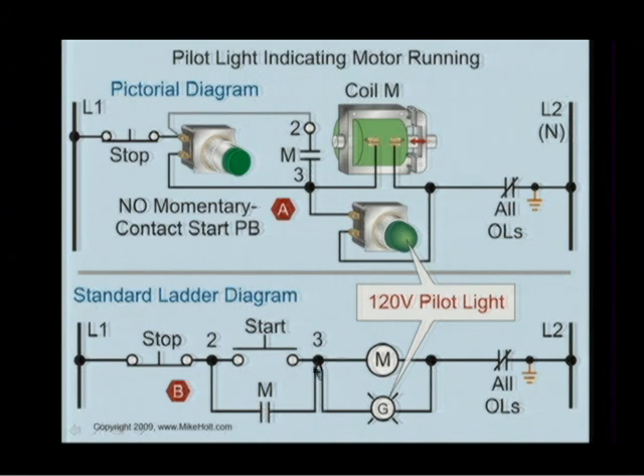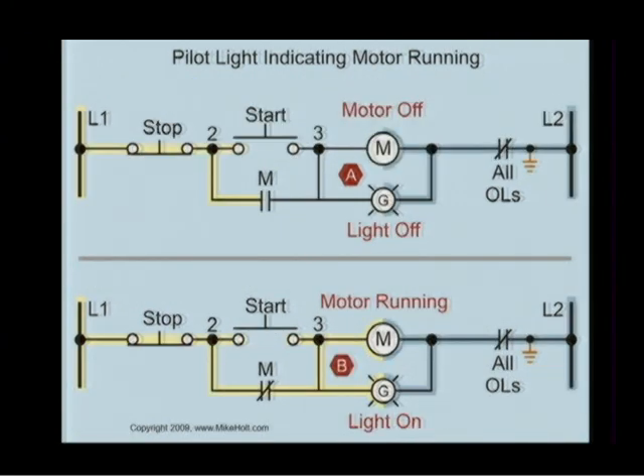I energize the coil. It closes its associated contacts, which is the M contacts, the holding contacts, interlocking contacts, the latching contacts, the securing contacts, whatever you want to call this. It's closing the main contacts that we're not seeing to the motor, right? The motor runs. And because this auxiliary contact is being held closed by the M coil, it now remains energized. So now the light shows green. Basically, if you put your lights in parallel with your coil, then when the coil is energized, since the light is in parallel with the coil, it will receive the same voltage, right? Laws of parallel. In this case, we're using a green light saying yes, the motor's running.